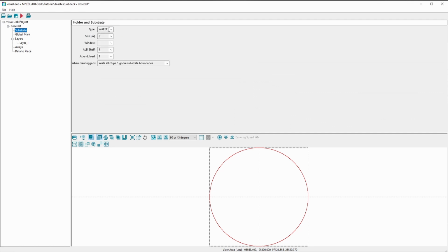You'll notice that when you're on a wafer type, there are not too many choices here, and that is because most of the cassettes we have are multi-piece cassettes. So now you can choose between all the windows of the cassettes that you would usually be able to choose on the 9500 system. Now, we will be exposing a 2-inch wafer in this case, so I will use slot 2A. For my exposure, I will expect that this cassette will be loaded from slot number 9. And after exposure, I would like to load in cassette number 1.